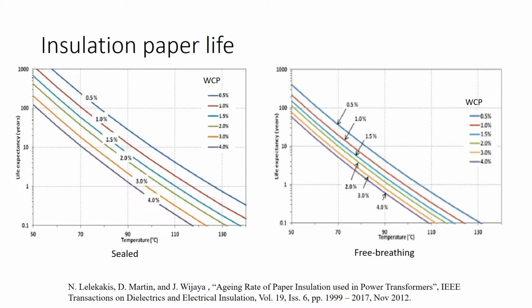So we have here two graphs. Transformers can be either sealed or free breathing. For smaller units, especially over here, most of the new ones are sealed, so the transformer paper is kept away from the oxygen in the air. That helps prevent it from degrading. On the right hand side, we've got our free breathing units. A lot of transformers here may be mid MVA, maybe in the range of tens of MVA, those sorts of ranges.